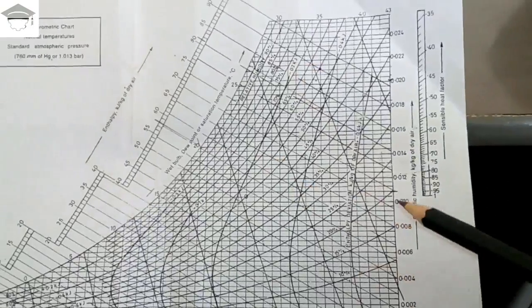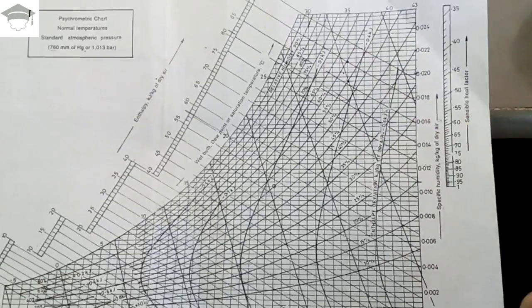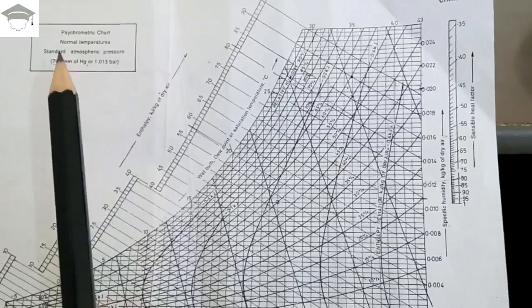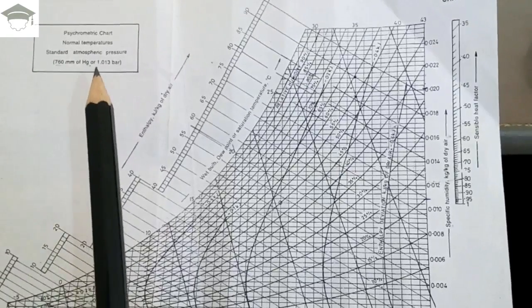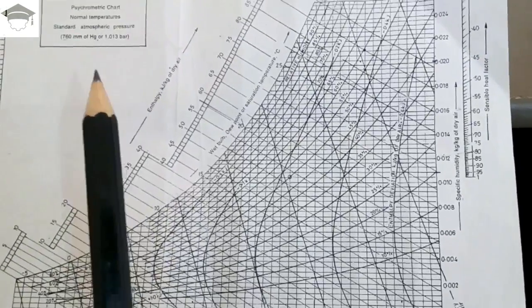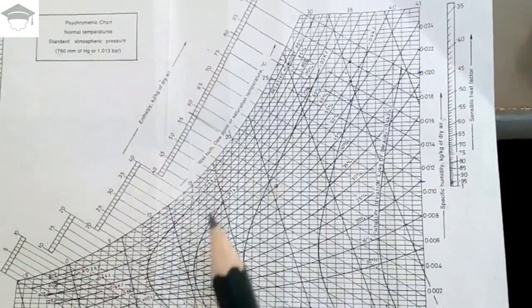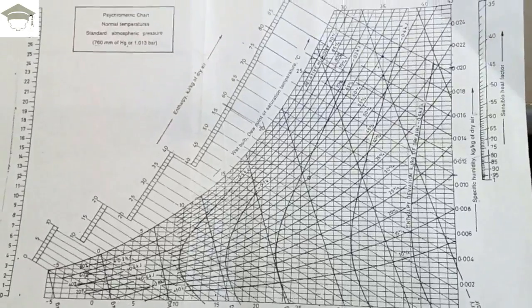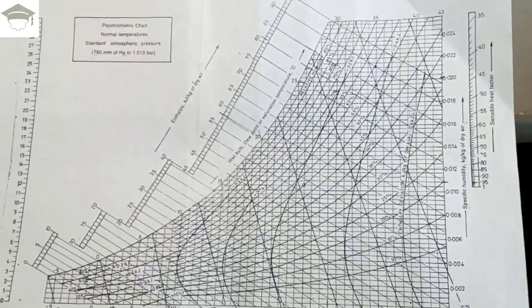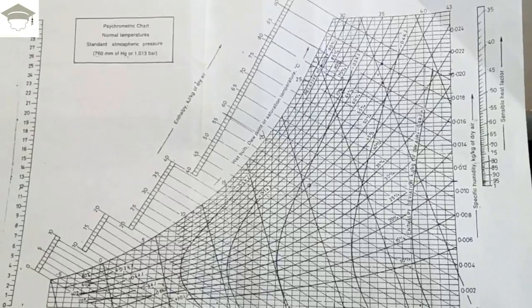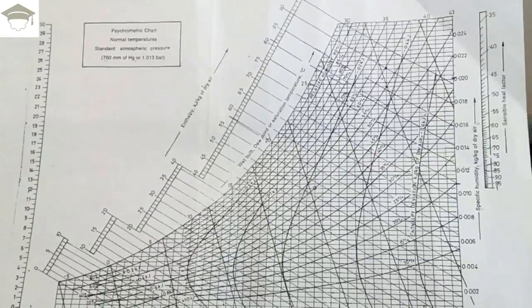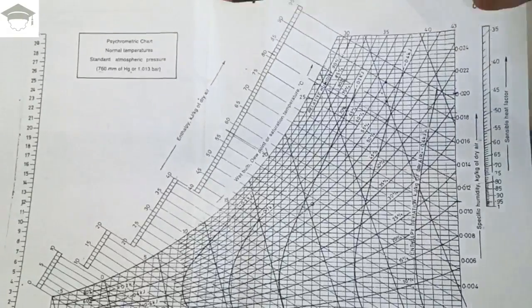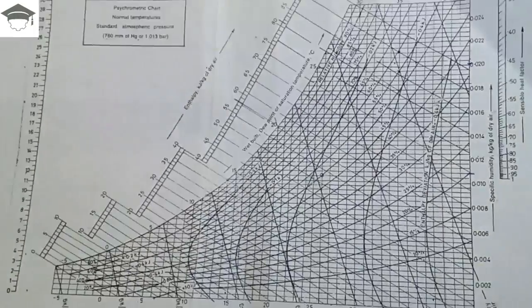These are the basic properties shown on the psychrometric chart. Remember that the psychrometric chart is drawn at 1 atm pressure — that is 760 mmHg or 1.01325 bar — which is standard atmospheric pressure. If the pressure in a question is different, you cannot use the psychrometric chart and must use the relations instead. In the next video I'll explain how to solve those questions.